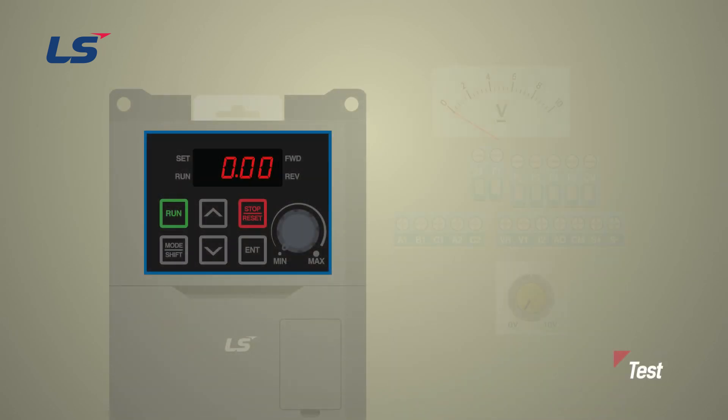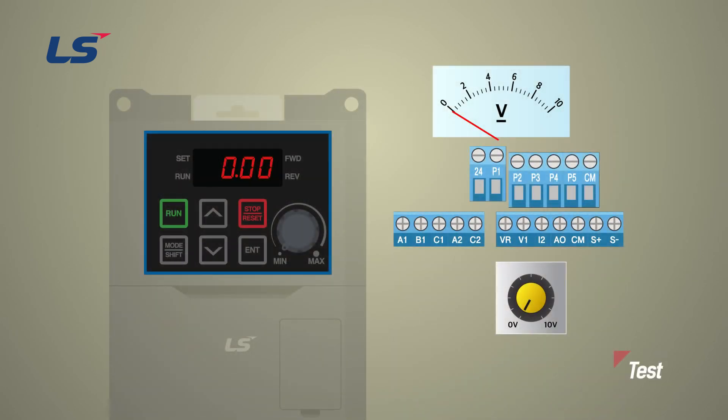Next, let's run the test under the parameter conditions set above. Wire the potentiometer using internal power source to the VR, V1, and CM terminals, then rotate the potentiometer and verify that the target frequency changes. Below 2 V, the frequency command becomes 0 hertz.